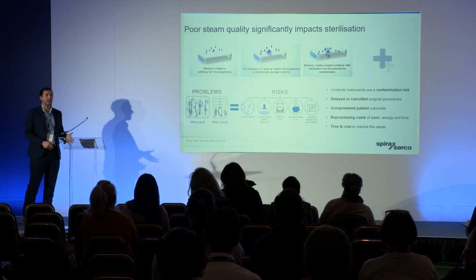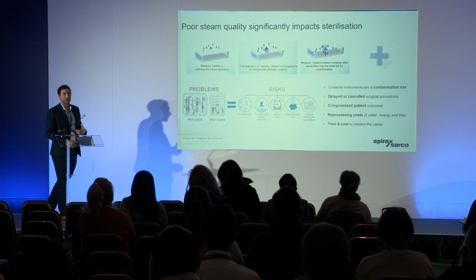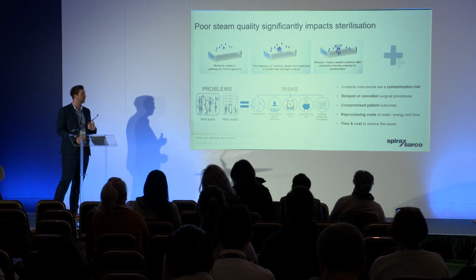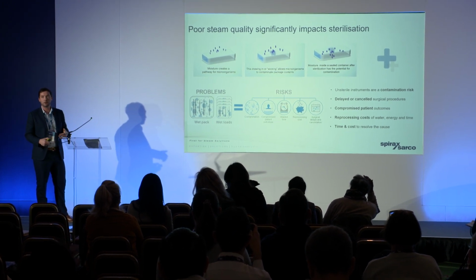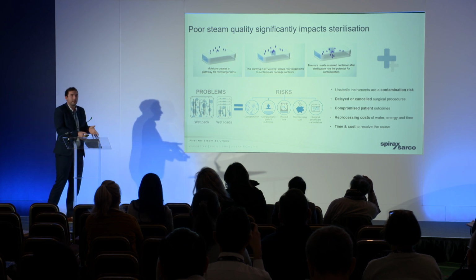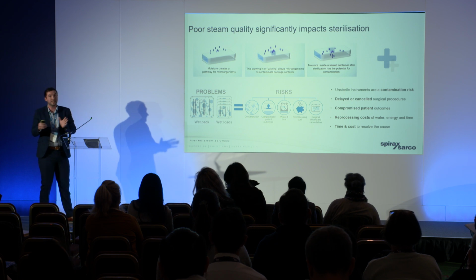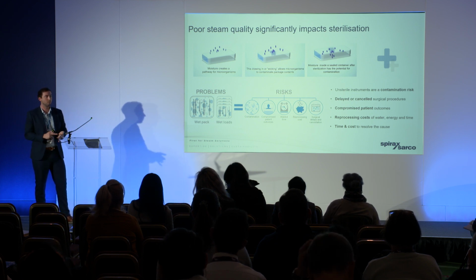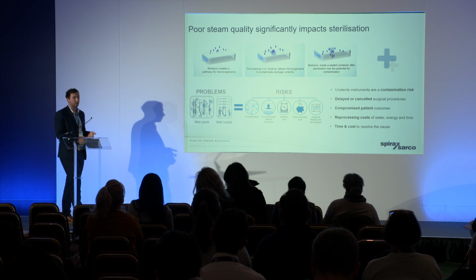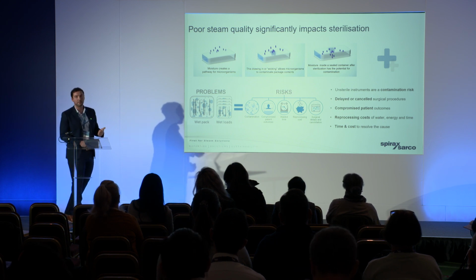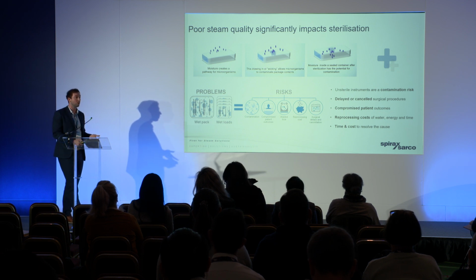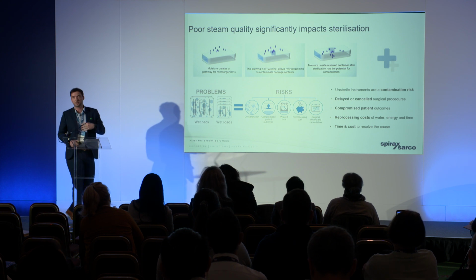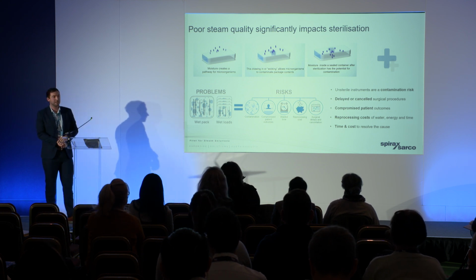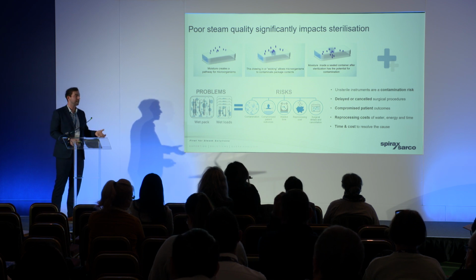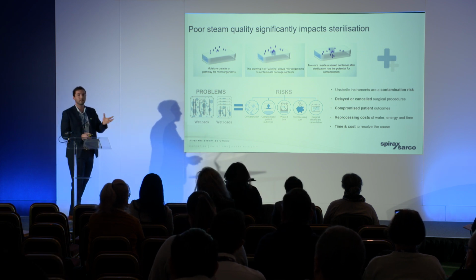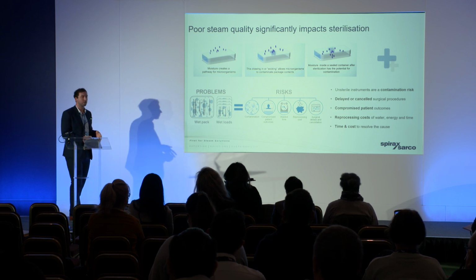I've just talked through a few of the impacts of not having good quality steam. I know the previous presentation was all about optimizing how many loads you can get through, not missing those, not delaying surgery. This is ultimately the patient's care at the end of it. But what we see on the plant room side is reprocessing, wet packs, problems with sterilization. Ultimately, all that means is added time and cost in either reprocessing or finding the cause of the problem. One thing we want to get across today is the reason Chris has spent many hours of his life validating our technology: we can guarantee good quality steam into the sterilizer, so we're narrowing down the options for where these problems are coming from.